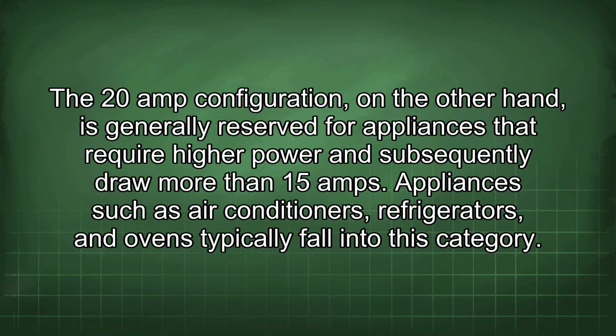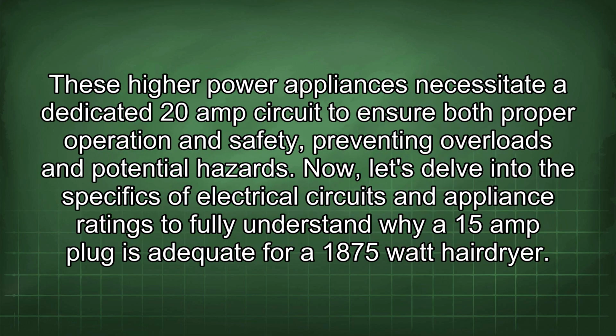The 20 amp configuration, on the other hand, is generally reserved for appliances that require high power and subsequently draw more than 15 amps. Appliances such as air conditioners, refrigerators, and ovens typically fall into this category. These higher power appliances necessitate a dedicated 20 amp circuit to ensure both proper operation and safety, preventing overloads and potential hazards. Now let's delve into the specifics of electrical circuits and appliance ratings to fully understand why a 15 amp plug is adequate for a 1875 watt hairdryer.